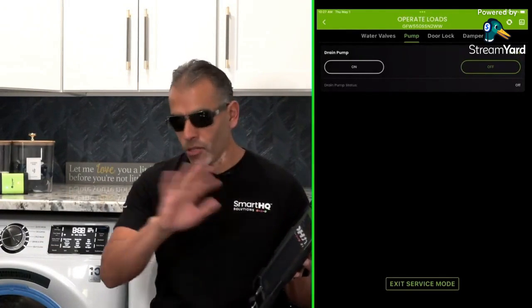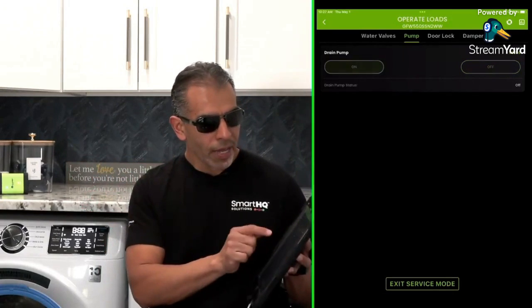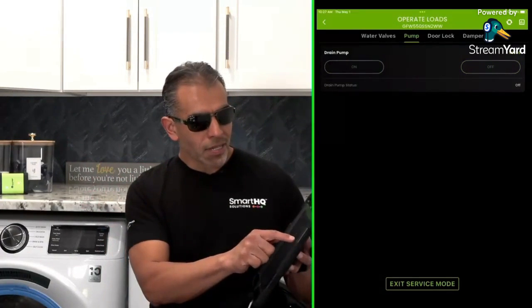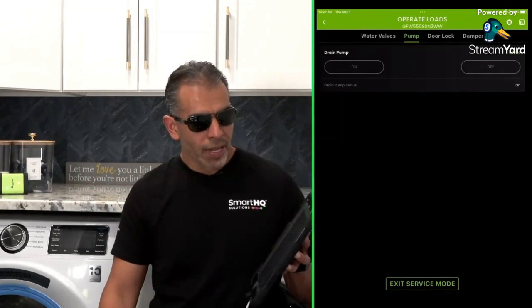We can turn it on again - I'm going to go ahead and turn it on one more time. There's no water that's going to drain, but we're going to turn it on. Take a look at the status, it changes from off to on, indicating that my main board is sending power to the drain pump in this particular case. So let's turn it off.